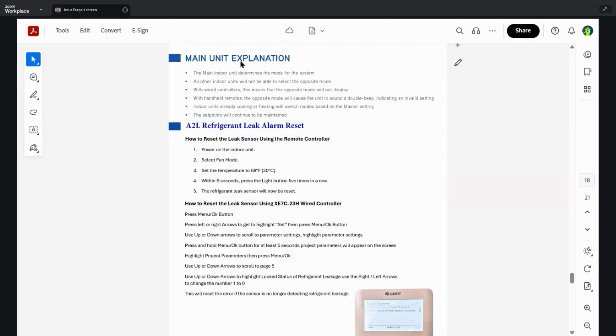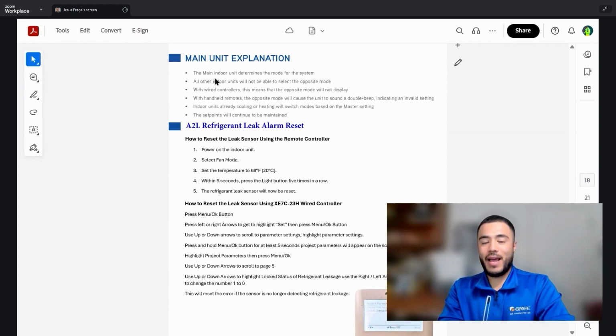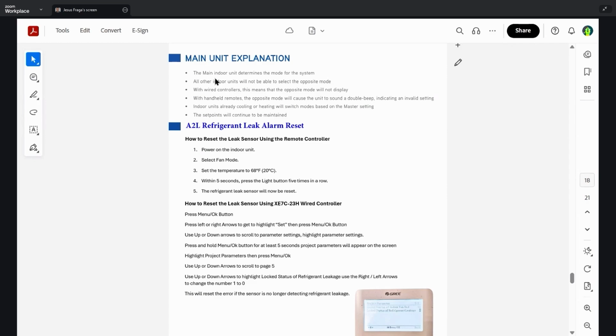So as I stated earlier, here's an explanation of what a main unit actually means. There's one wired controller that's going to be designated as the main indoor unit. We need to not confuse this with main indoor wired controller. So the main difference is each system that has a wired controller will be designated as a main wired controller, but there's only one main indoor unit. That main indoor unit is what controls the mode from heating to cooling. So if you go to a controller and you try to change mode from heating to cooling and it doesn't give you the option, we know that that's a subordinate controller.